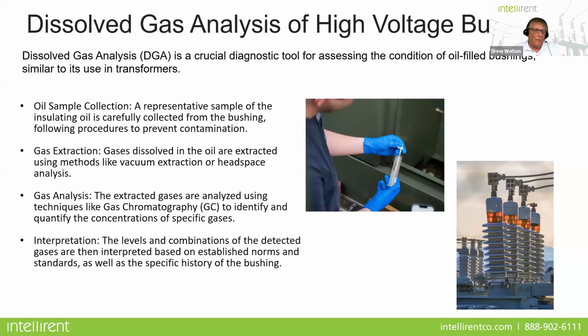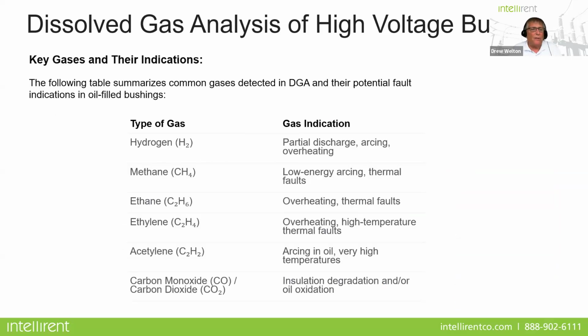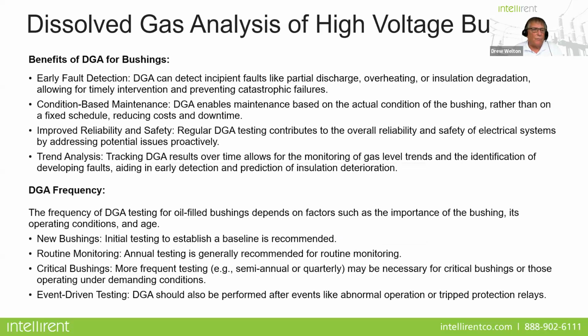Taking oil samples of your oil-filled bushings is just as important. What we want to look for are indications of particular gases. Hydrogen indicates partial discharge, arcing and overheating. Methane indicates low energy arcing or thermal faults. Ethane is a result of overheating and thermal faults, as is ethylene. Acetylene is going to be the bad one. That's arcing in the oil at very high temperatures. And CO and CO2 indicate insulation degradation or oxidation. It is very similar to what you see in a transformer.